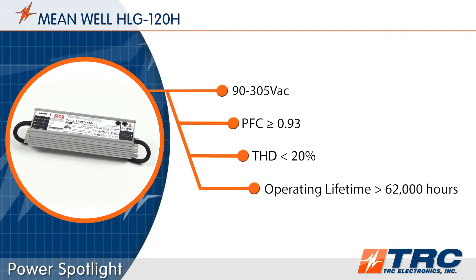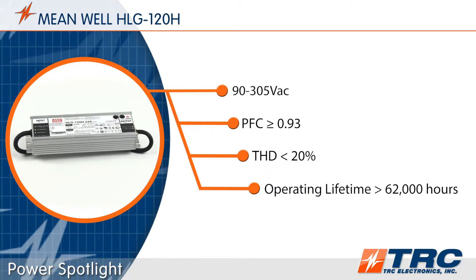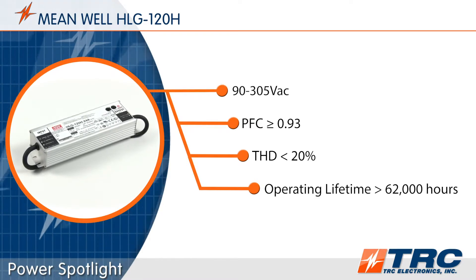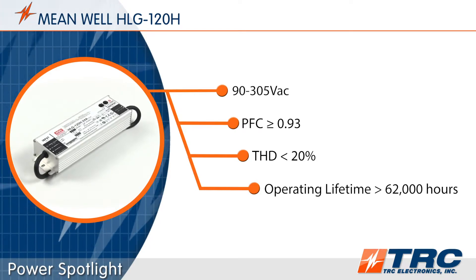All models feature a wide input voltage range of 90 to 305 volts AC, meaning these drivers can operate in 120-volt, 220-volt, or 277-volt lighting systems. These performance features will help lighting designers meet the DesignLights Consortium standards for solid-state lighting that existed at the time of this recording.